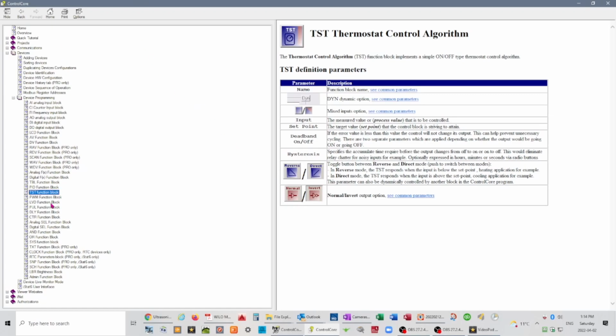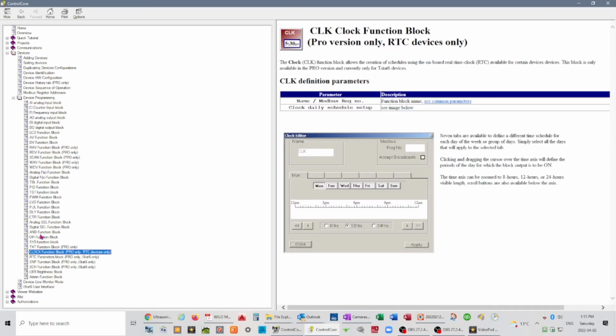Clock function, that's something I'm going to be looking at to act on the system based on the time of day. So for instance, I'm going to be looking at seeing how to program this so if it is a sunny day outside in the wintertime, to allow the buffer tank to chill down, in other words, don't maintain its set point temperature, and then open up zone valves in zones that are significantly over the set point.